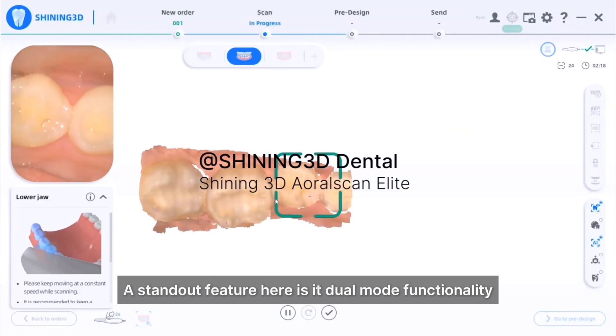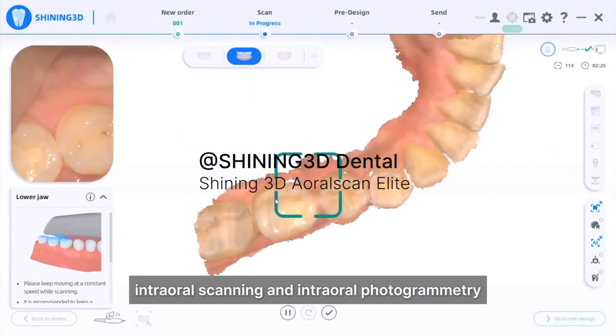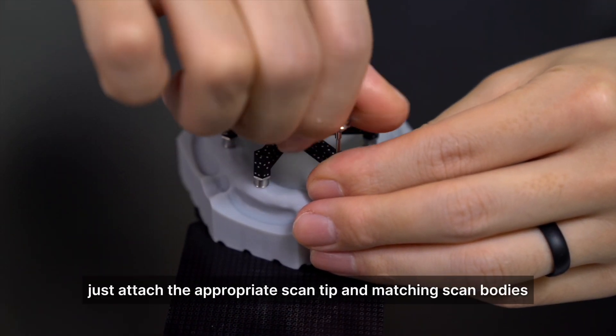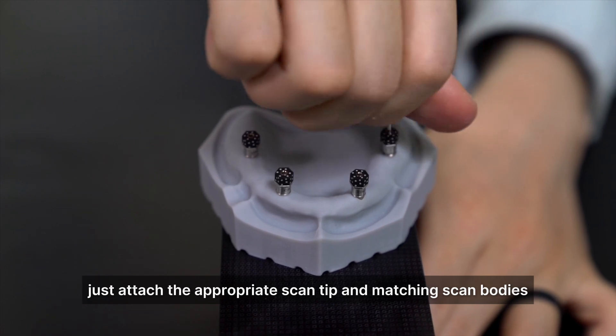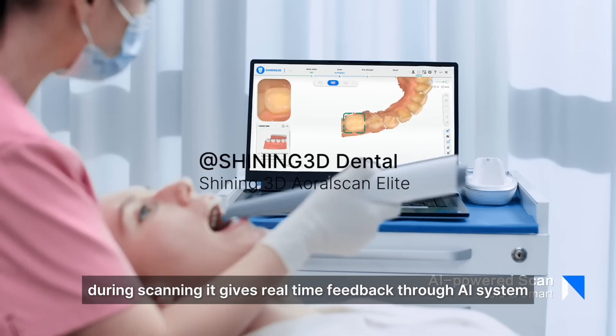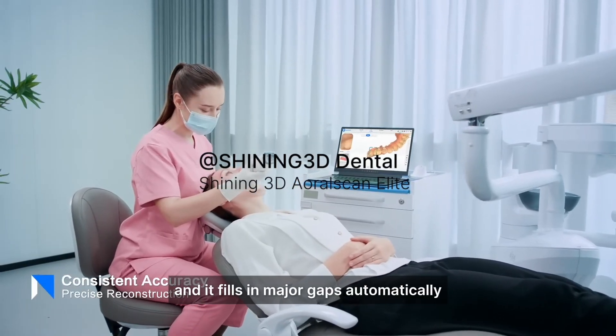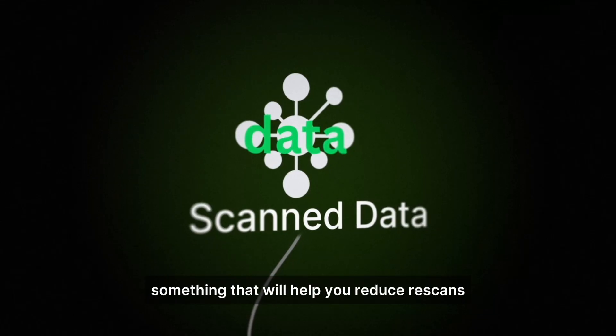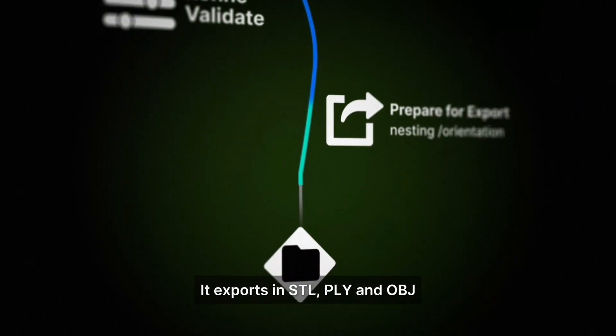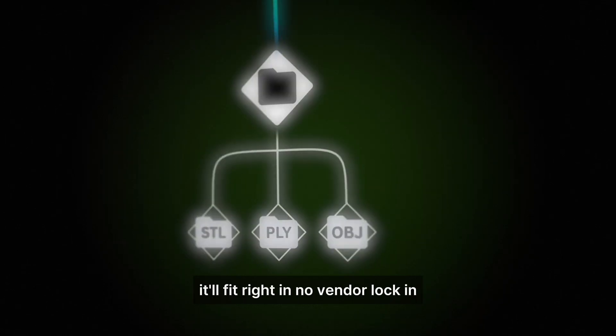A standout feature here is its dual-mode functionality. You can switch between standard internal scanning and internal photogrammetry for full-arch implant precision. Mode switching is simple — just attach the appropriate scan tip and matching scan bodies. During scanning, it gives real-time feedback through AI systems. You can actually see where to move next, and it fills in major gaps automatically, something that will help reduce rescans. It exports in STL, PLY, and OBJ, so if you're already working with third-party CAD/CAM, it'll fit right in — no vendor lock-in.